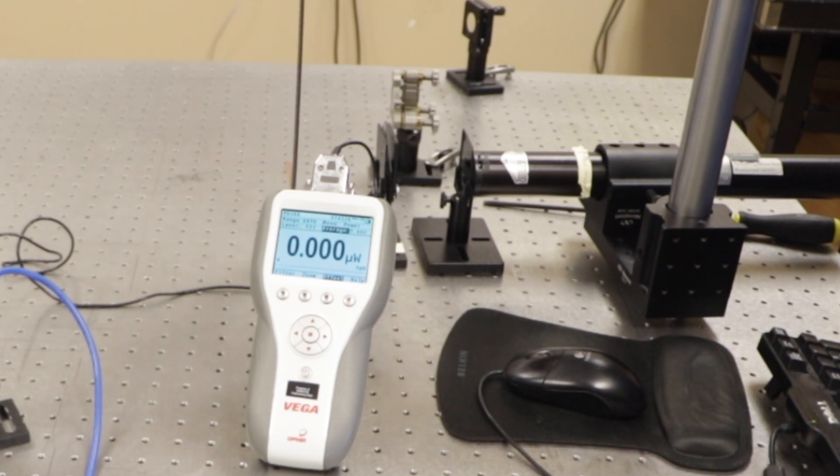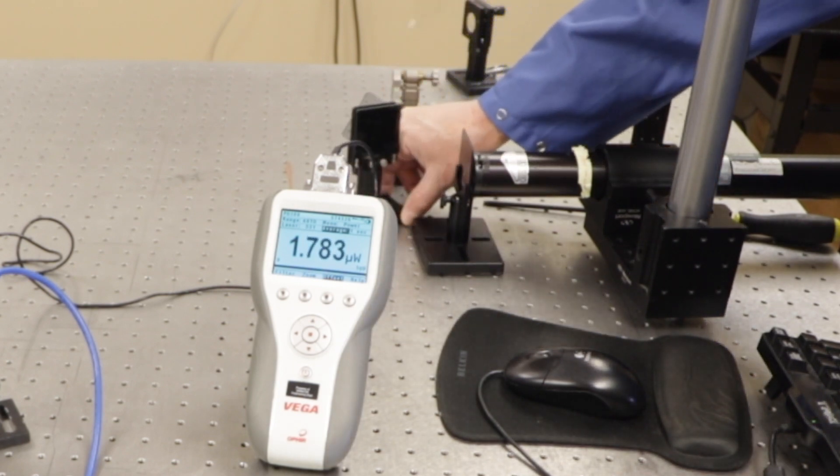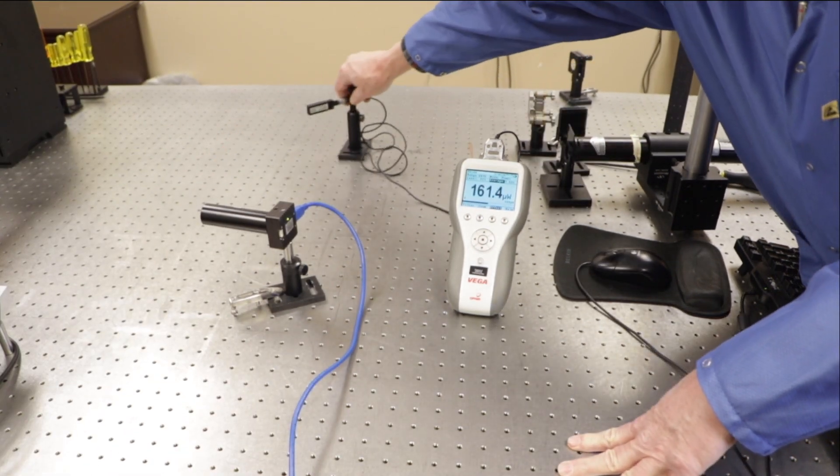We block the beam to zero the offset on the meter. Unblocking the sensor shows the attenuated beam contains 1.6 microwatts. When we remove the ND filters, the beam measures 160 microwatts, 100 times more powerful.